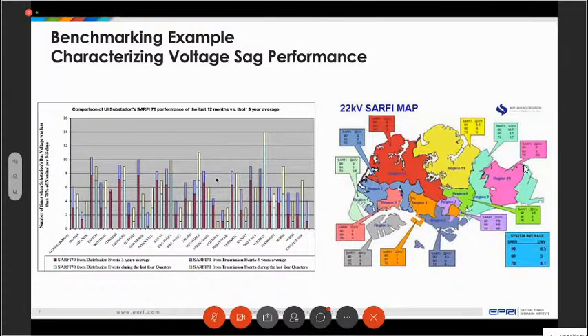And so that's still important because the industry in Singapore is a lot of semiconductor industry and industrial plants that are very sensitive to variations in the voltage. So if they get a voltage sag where the voltage goes below 70%, they could lose production of millions of dollars worth of semiconductor chips and have to scrap those chips. So power quality is an absolutely critical issue in Singapore, and they're one of the leaders in the world in researching power quality phenomena. It's interesting that they can provide this information for their industrial customers about how many voltage sags they can expect per year, depending on where they're located in Singapore. So a very interesting way to present results.